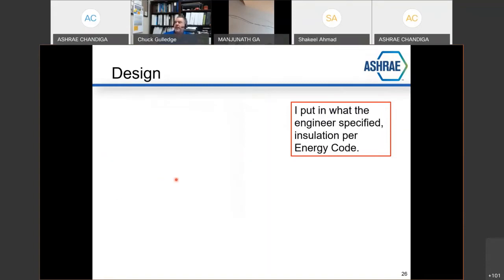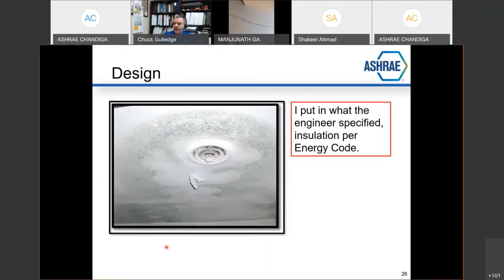I put in what the engineer specified, insulation per energy code. So what happens when you just put your head in the sand and do what the code says and don't think about building dew point and moisture control and condensation? This is what happens. This is very typical through hot, humid climate scenarios. Minimum insulation per energy code does not, I repeat, does not address condensation control on cold surfaces.